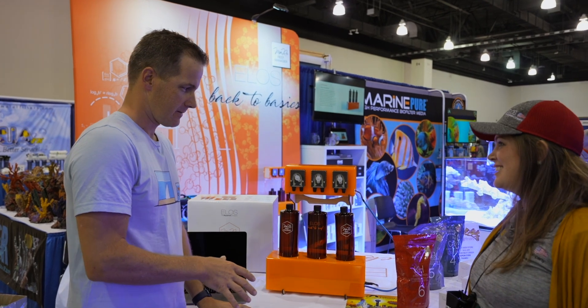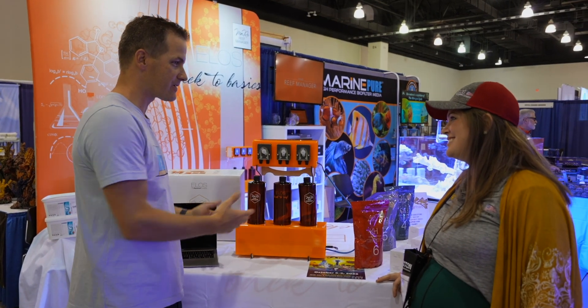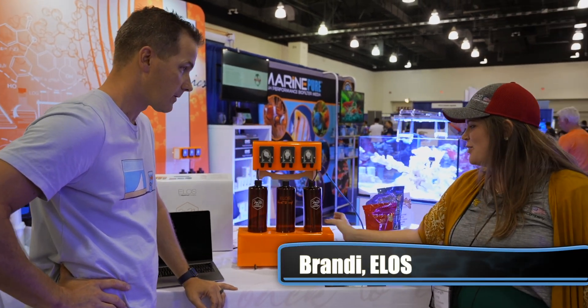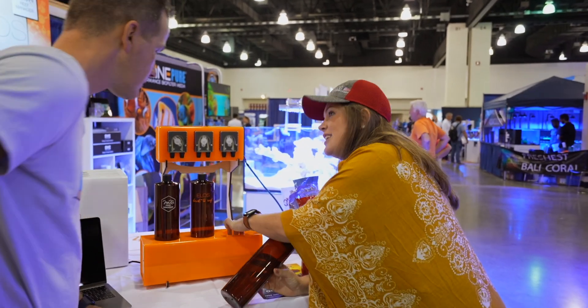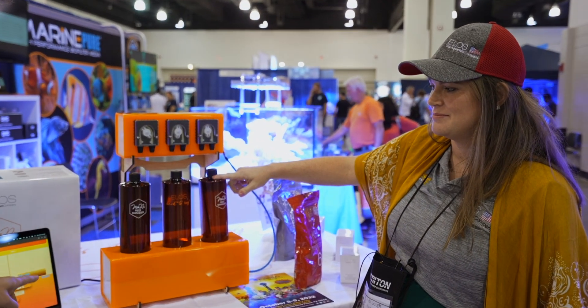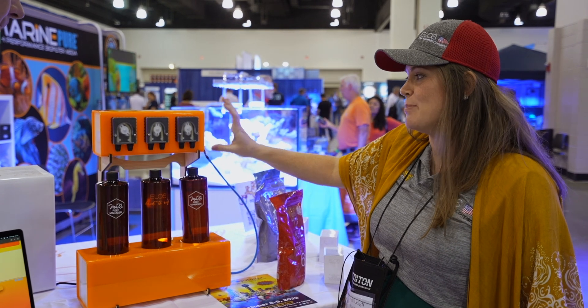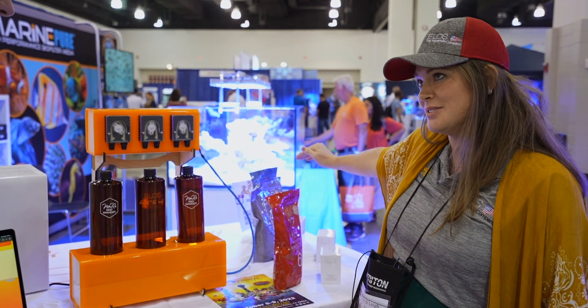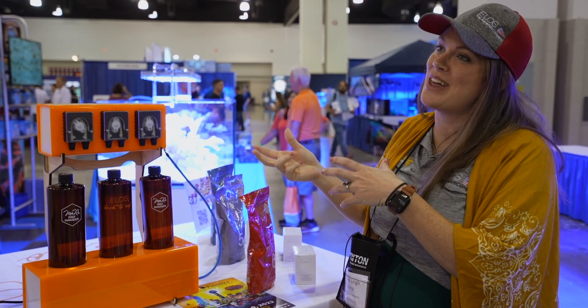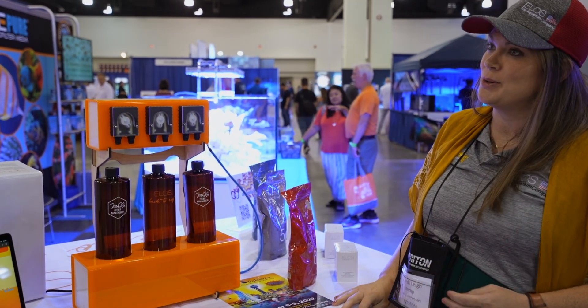This is clearly a dosing pump, but here's where some of the magic sauce is. When you lift this up, you can see down in here that we have some scales. It's giving me milliliters for weight based on density. We currently have the Elos chemicals in here and we know the density of those chemicals — how many grams are in each milliliter — so we know exactly how many milliliters equate to a gram being dosed.